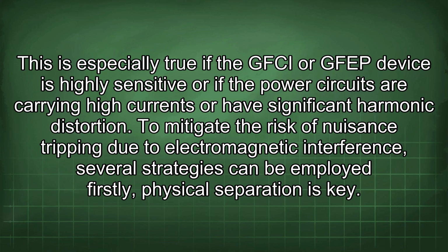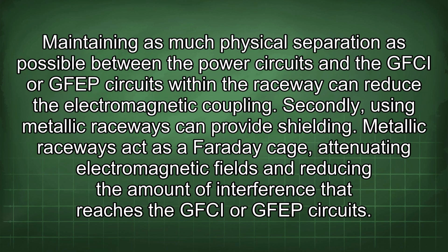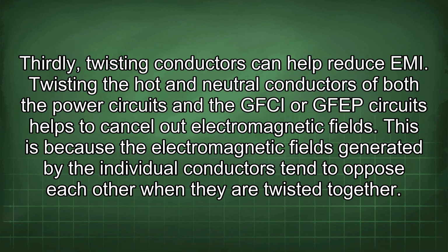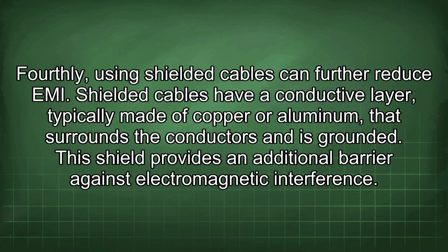To mitigate the risk of nuisance tripping due to electromagnetic interference, several strategies can be employed. Firstly, physical separation is key. Maintaining as much physical separation as possible between the power circuits and the GFCI or GFEP circuits within the raceway can reduce the electromagnetic coupling. Secondly, using metallic raceways can provide shielding. Metallic raceways act as a Faraday cage, attenuating electromagnetic fields and reducing the amount of interference that reaches the GFCI or GFEP circuits. Thirdly, twisting conductors can help reduce EMI. Twisting the hot and neutral conductors of both the power circuits and the GFCI or GFEP circuits helps to cancel out electromagnetic fields. This is because the electromagnetic fields generated by the individual conductors tend to oppose each other when they are twisted together.